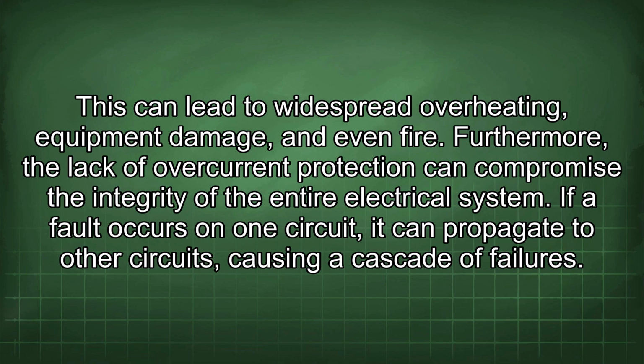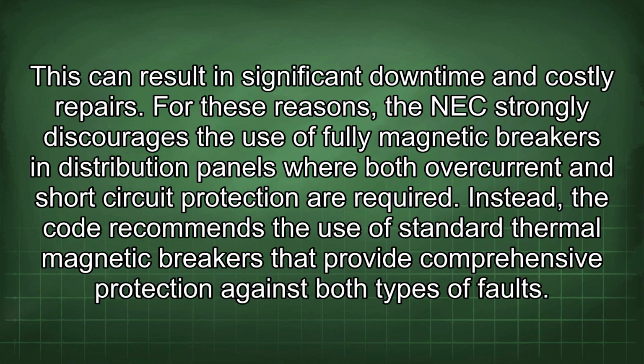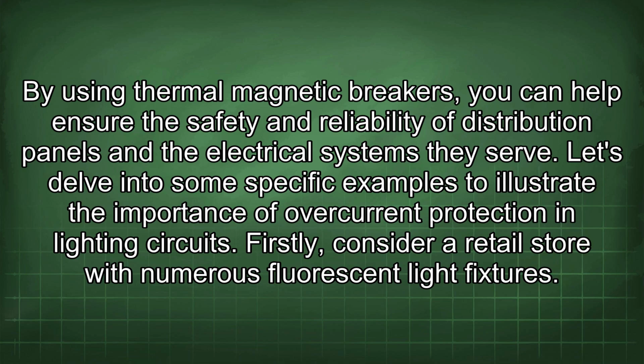Furthermore, the lack of overcurrent protection can compromise the integrity of the entire electrical system. If a fault occurs on one circuit, it can propagate to other circuits, causing a cascade of failures. This can result in significant downtime and costly repairs. For these reasons, the NEC strongly discourages the use of fully magnetic breakers in distribution panels where both overcurrent and short-circuit protection are required. Instead, the code recommends the use of standard thermal magnetic breakers that provide comprehensive protection against both types of faults. By using thermal magnetic breakers, you can help ensure the safety and reliability of distribution panels and the electrical systems they serve.